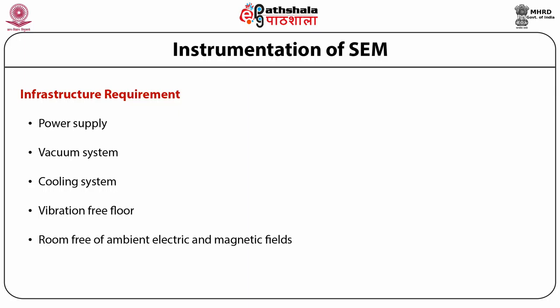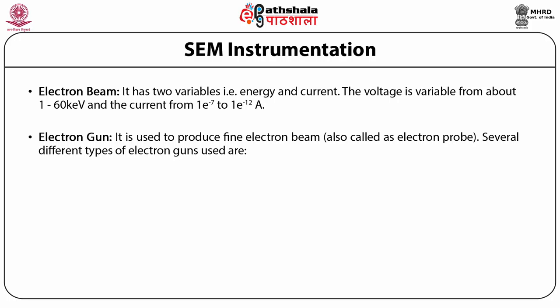The room must be free of ambient electrical and magnetic fields. Scanning electron microscopy instrumentation: let us now discuss the description of each component. This figure shows the schematic of a SEM. The electron beam has two variables: energy and current. The voltage is variable from about 1 to 60 keV and the current from 1×10⁻⁷ to 1×10⁻¹² amperes. These values are specific to the instrument model. The second component is the electron gun, which is used to produce a fine electron beam called an electron probe.